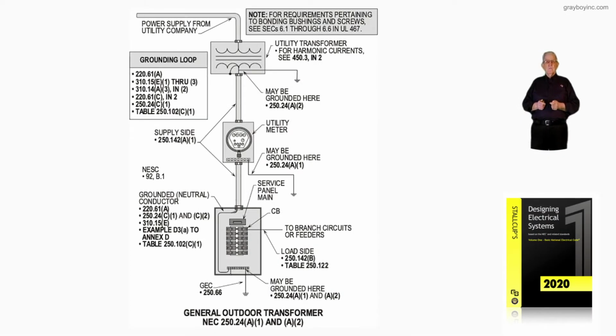This illustration deals with general outdoor transformers. And in the previous illustration, we talked about 250.24(A)(2), which said you had to ground the transformer outside. Then 250.24(A)(1) and through those sections of (A) deal with grounding at the service. So we ground the transformer, we ground at the service equipment. And we could even put a supplementary ground at the meter if the utility would allow us to ground in the meter.